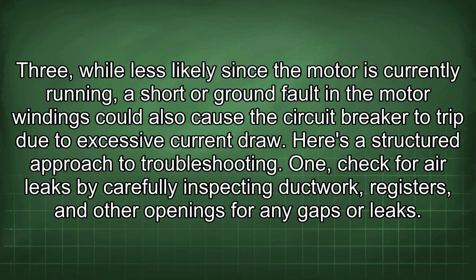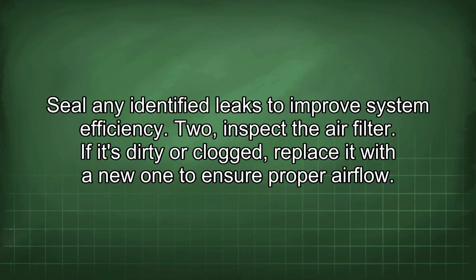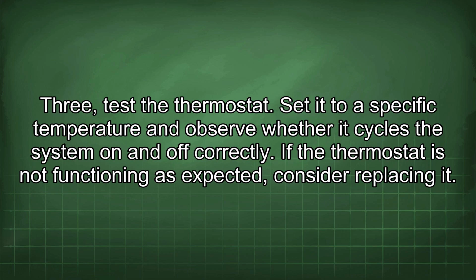Here is a structured approach to troubleshooting. 1. Check for air leaks by carefully inspecting ductwork, registers, and other openings for any gaps or leaks. Seal any identified leaks to improve system efficiency. 2. Inspect the air filter. If it's dirty or clogged, replace it with a new one to ensure proper airflow. 3. Test the thermostat. Set it to a specific temperature and observe whether it cycles the system on and off correctly. If the thermostat is not functioning as expected, consider replacing it.